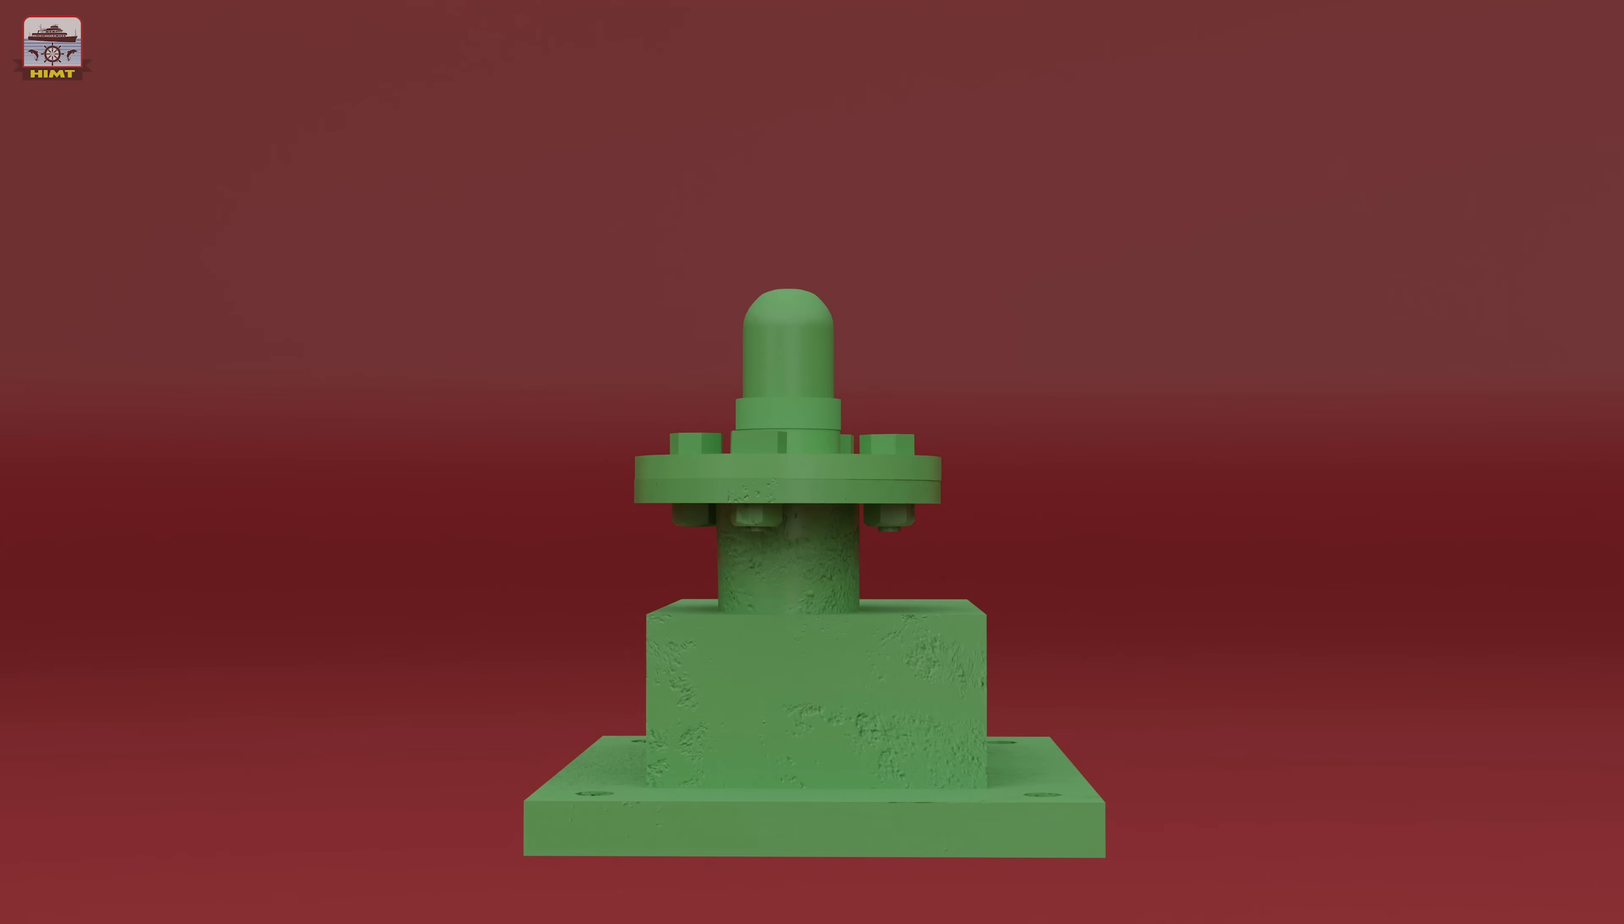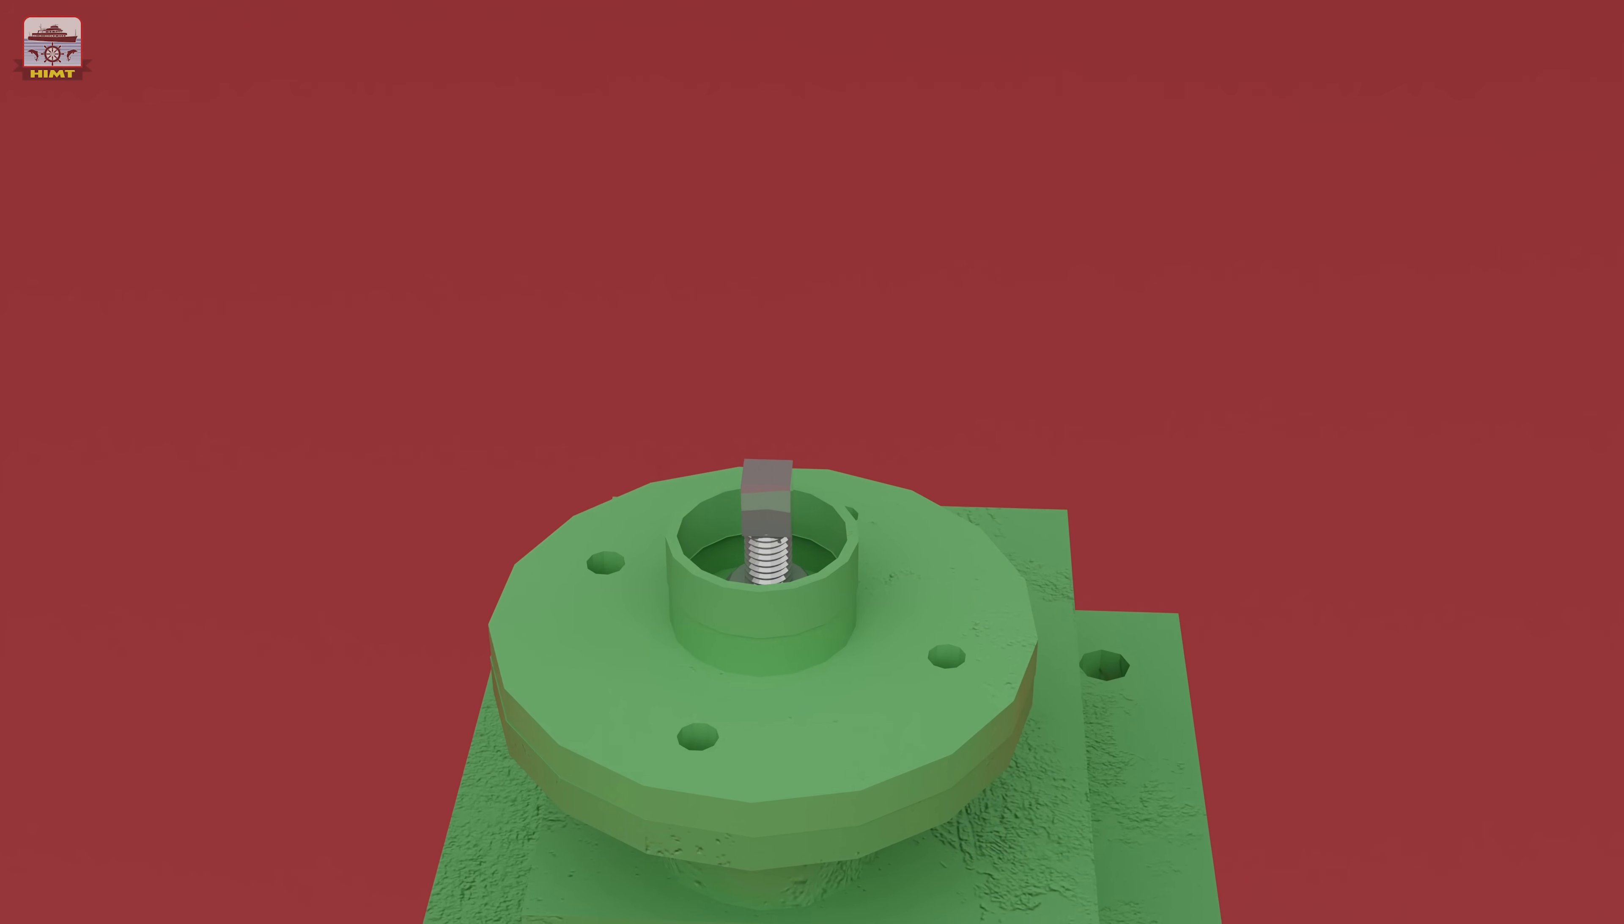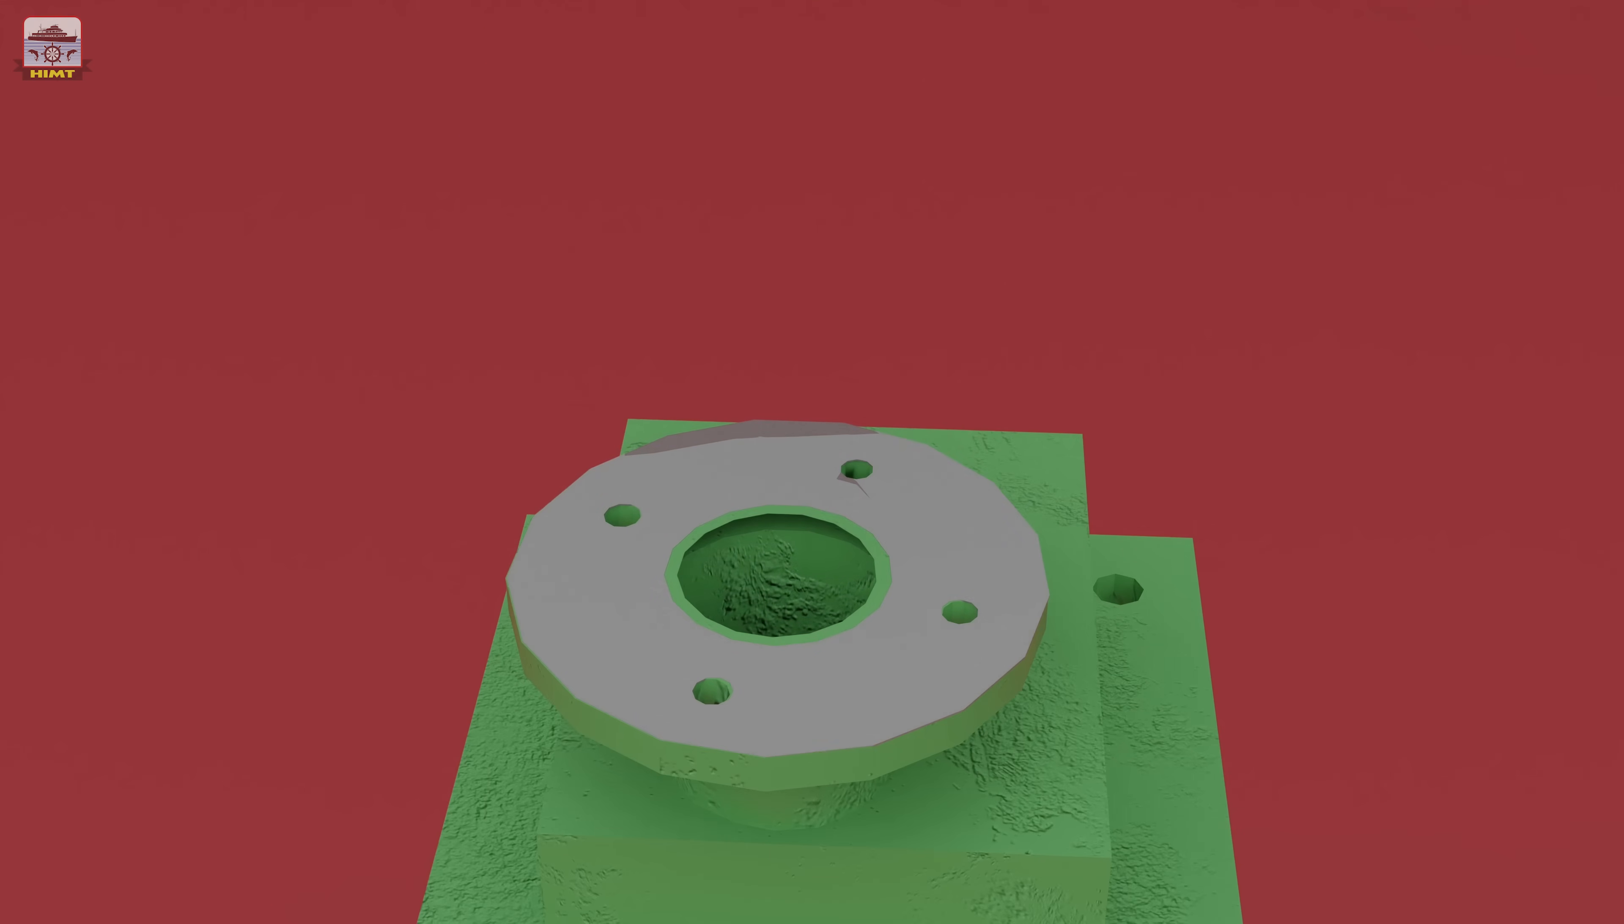Now, remove the cap located on top of the relief valve, providing access to the valve's internals. Now, remove the securing bolts and nuts of the flange meant for the adjustment screw. Gently remove the adjustment screw, which plays a vital role in regulating the relief valve's operation. With the adjustment screw removed, carefully detach the flange from the relief valve assembly.